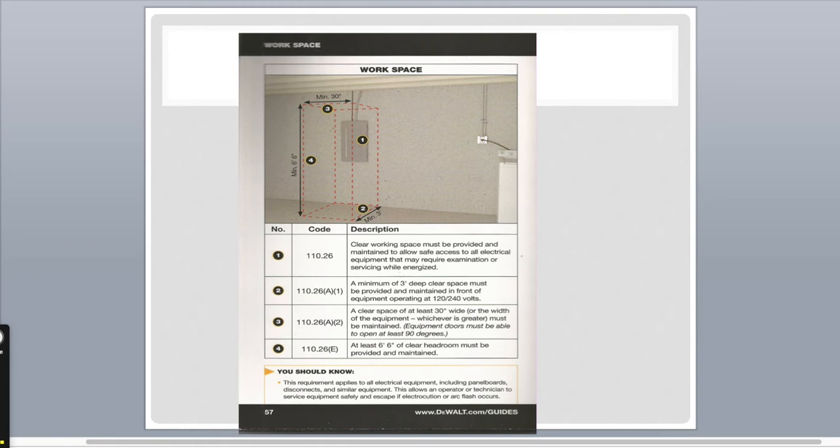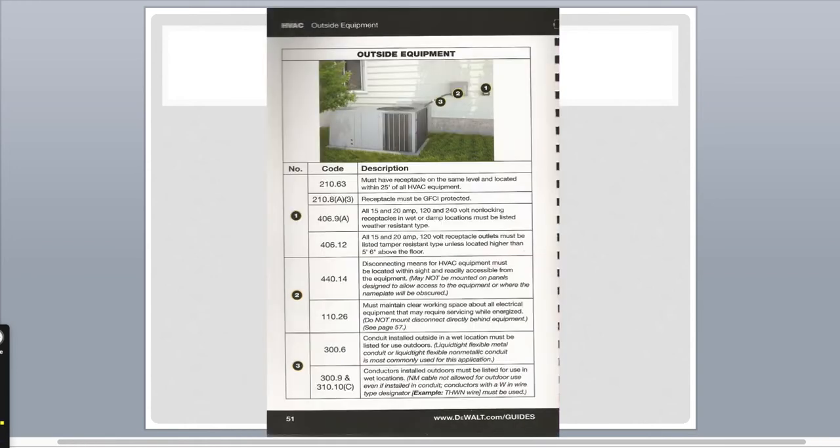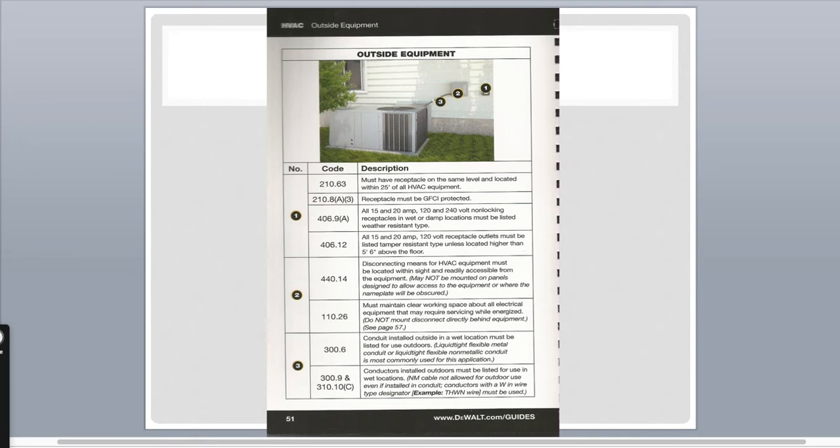The next one, for the AC guys, shows you must have a receptacle on the same level and located within 25 feet of AC equipment, HVAC equipment. Anybody who's been on a job and didn't have that, you understand how it's dangerous. It's also a complete inconvenience also.